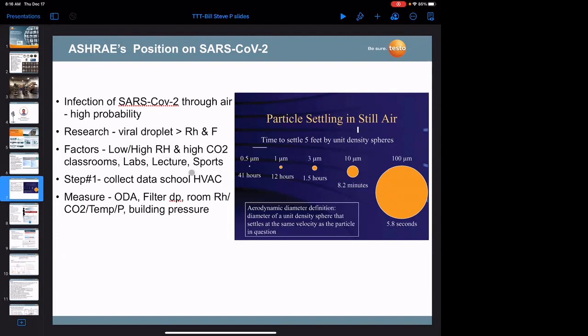Once we do that, we want to also collect the data after we've optimized the HVAC system to make sure we're controlling these variables. You do that by measuring outside airflow, pressure drop across your filters, room relative humidity, CO2, temperature, and building pressurization. I think you can see now where Testo is coming into this discussion with that last bullet point.